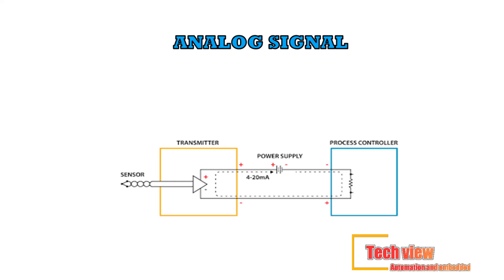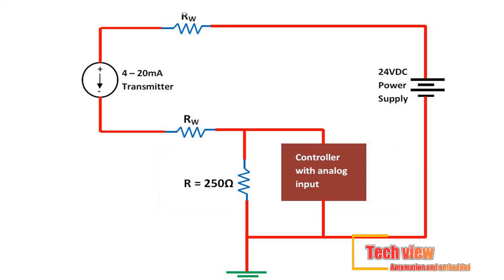Using current to transmit analog signals has the following advantages. Current signals are more immune to interference than voltage signals, since the value is unaffected by voltage drops in the conductors, stray thermocouples, contact resistance, and noise voltage due to capacitive and inductive coupling.